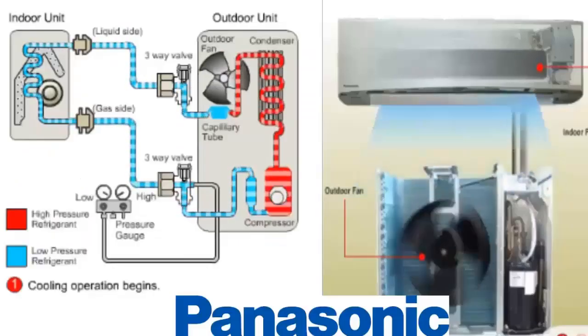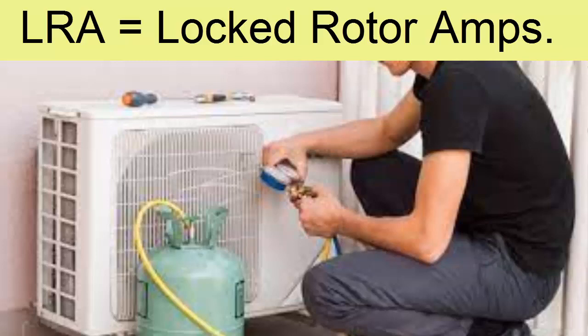8. When the current value measured with the clamp exceeds the LRA, it is highly likely that the compressor needs to be replaced because we are dealing with a severe mechanical or electrical problem.